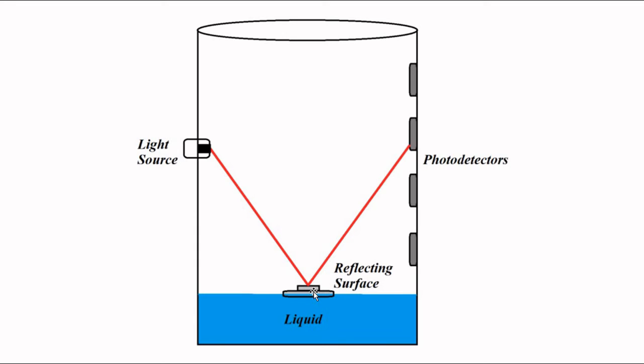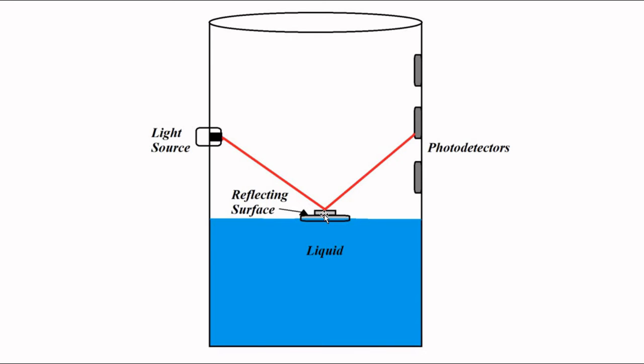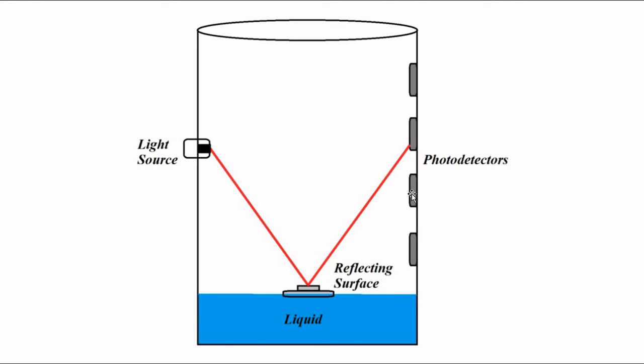The floating object has a reflecting surface — a mirror — placed on it. Light is focused on that surface, and based on the laws of reflection, the incident light gets reflected at the same angle toward the array of photo detectors. Depending on the liquid level, the reflected light is focused on one of the series of photo detectors. By determining which photo detector receives the reflected light, we can determine the level of liquid in the tank. This is a very simple technique for determining liquid level.